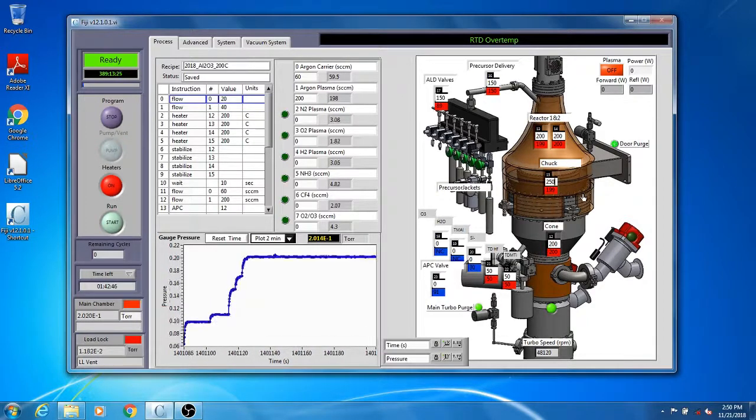The recipe does also have a provision to set up the temperature of the heaters as shown in the recipe, but it takes a significant time to get a stabilized desired heater temperature. Right now, the recipe shows all 4 heaters at 200 C, so we will keep it at 200 C.